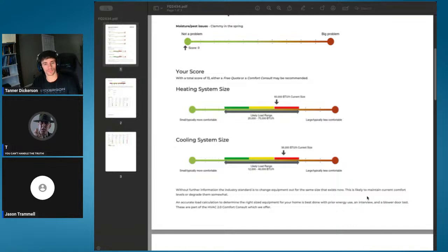The other thing about this process is it brings forward the conversation. If you oversize equipment, you may be on the hook for $10,000 to $15,000 of replacement ductwork in order to bring your equipment into manufacturer specified operating parameters—and it's still oversized. That just makes your short cycling worse and your temperature imbalance worse.